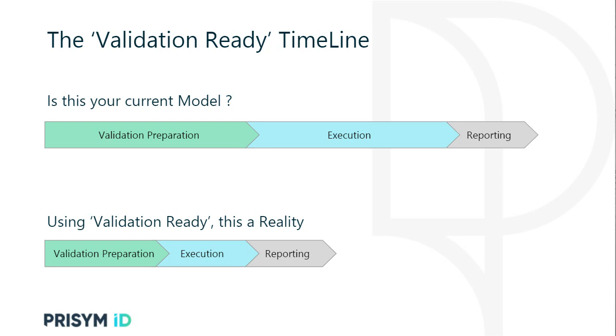Your business cases, they're demonstrating that you are fit for intended use. There's no advantage of retesting what your supplier has already done. Remember also that your supplier will undoubtedly have installation and operational qualifications you can leverage. It's the same principle for reports. The validation-ready documentation pack may have summary reports of supplier testing. These can be leveraged into your validation summary report, leaving you only to add the results of your testing.